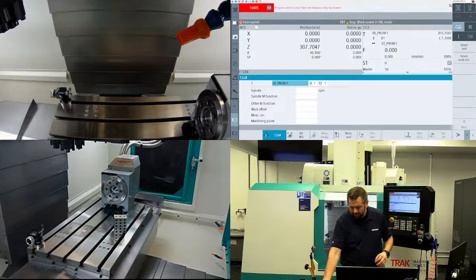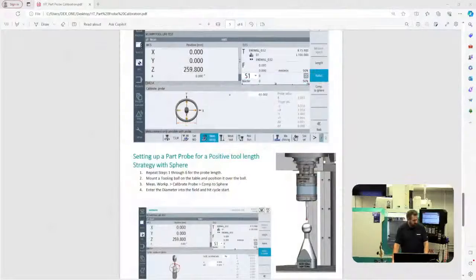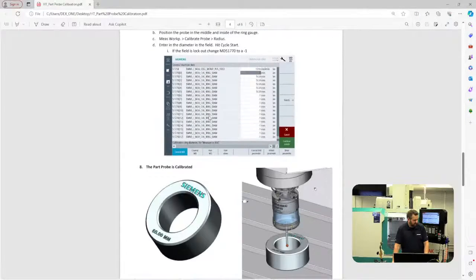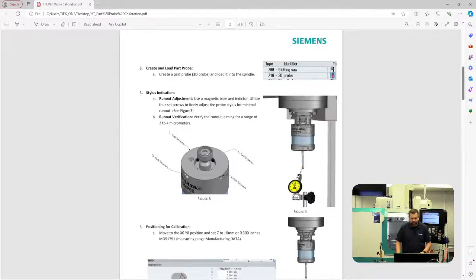So one of the things in the document that I've provided in the description, if we look at it, is we have kind of a layout of the inners of a probe body. So here we have 4 kind of positioning set screws that kind of go around the probe body and the tool holder, and then we have 2 that anchor it to the tool holder. So what I do is I kind of snug the 2 anchors tight, and then when I get my indicator on the stylus, I use those 4 set screws to fine tune it, and then I lock it all down once I'm pretty happy with it. One of the things I would say is usually kind of get it within 2 tenths run out would be kind of the goal. I always try to get it as close as I can to that.